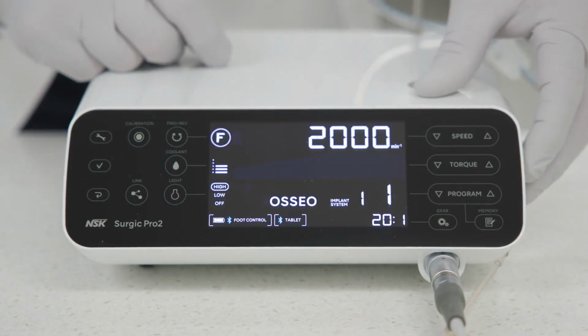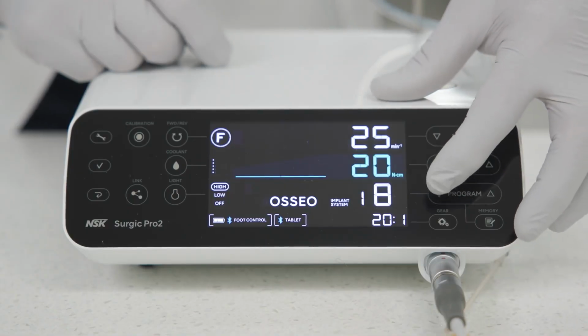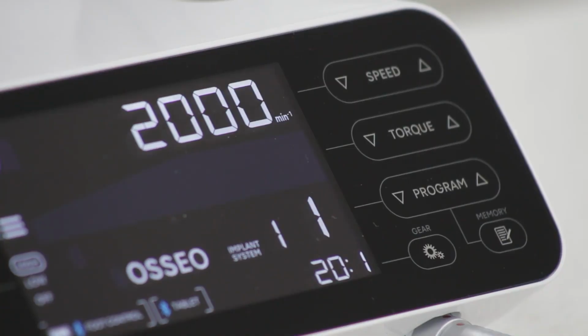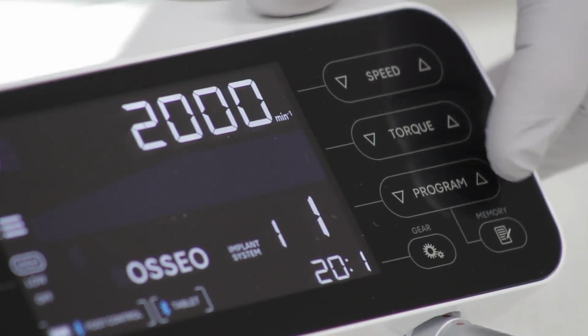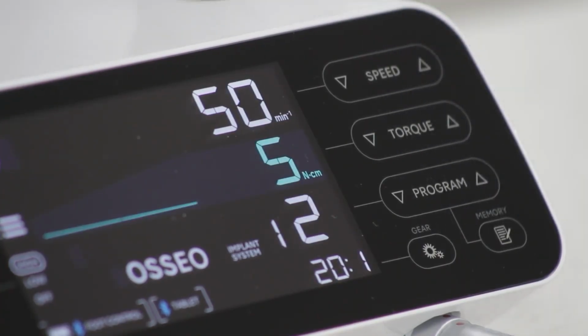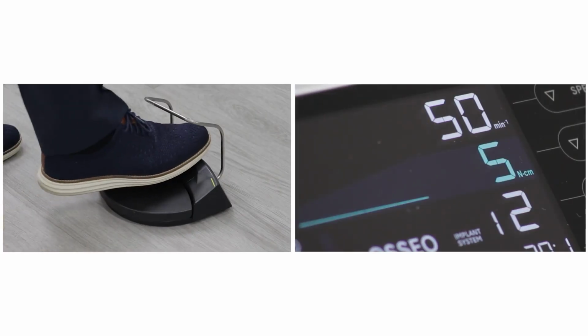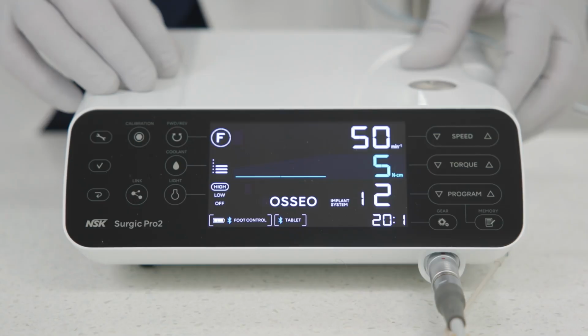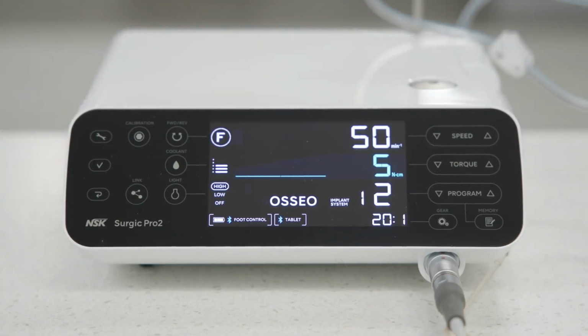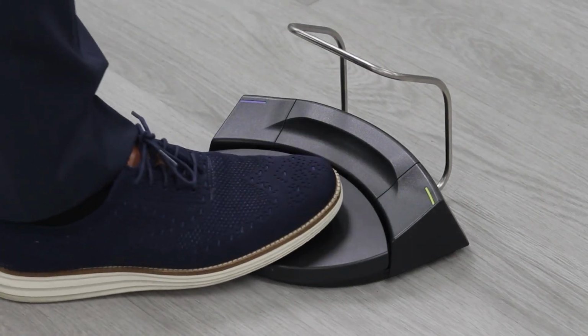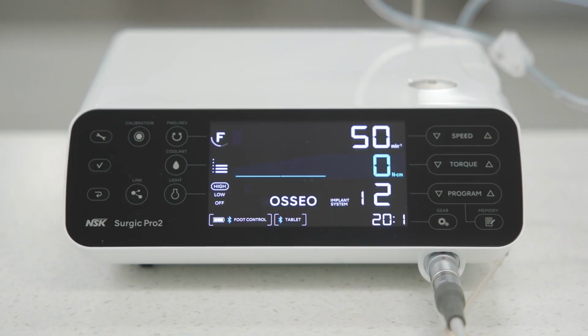If the foot control does not appear and connect after 30 seconds, replace the batteries in the foot control and try again. Select the desired preset program number by pressing the program up or down buttons on the panel or the middle button on the foot control. Verify the program details. Confirm or change the parameters if necessary. Step on the speed control pedal of the foot control to run the micromotor and the pump.